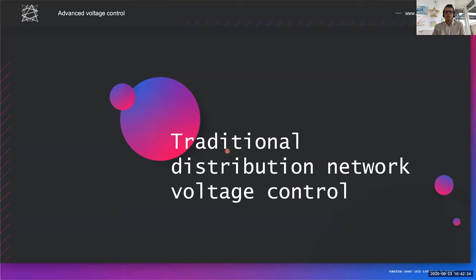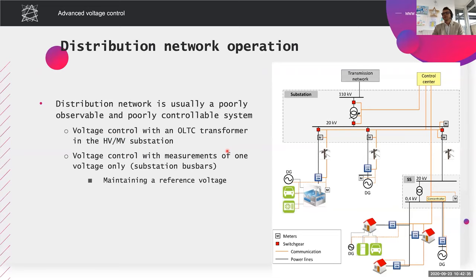Okay, so what solutions do we have? We will look at the traditional approach and then at the, let's say, advanced approach. So what is the traditional approach to voltage control in distribution networks? Usually today's distribution networks are poorly observable and poorly controllable systems. What does this mean? This means that there are not a lot of measurements at distribution level. And basically this means that the distribution system operator is not aware of the conditions in the distribution grid.